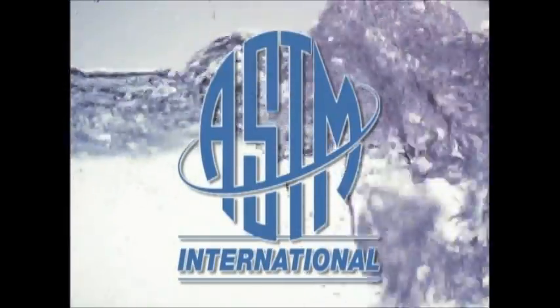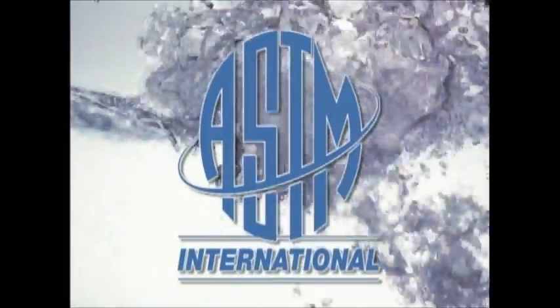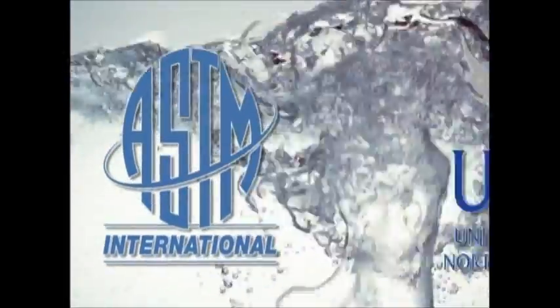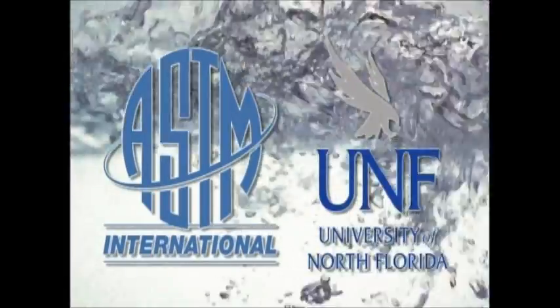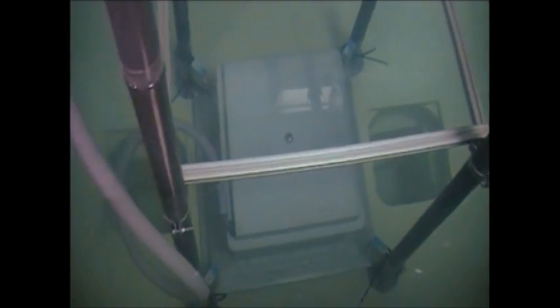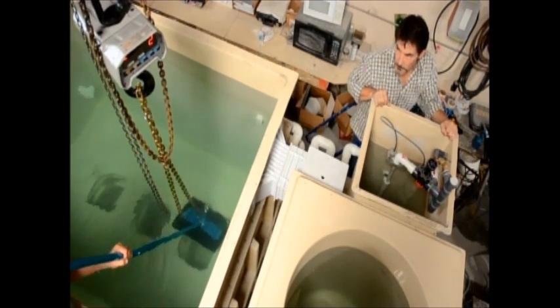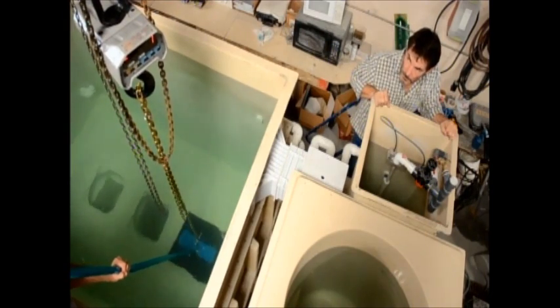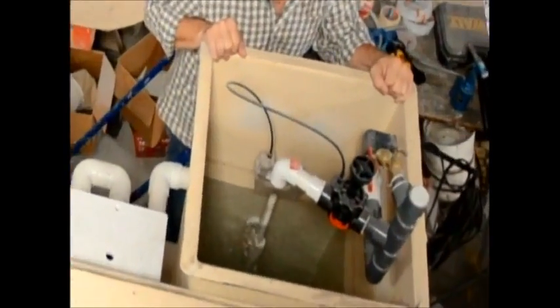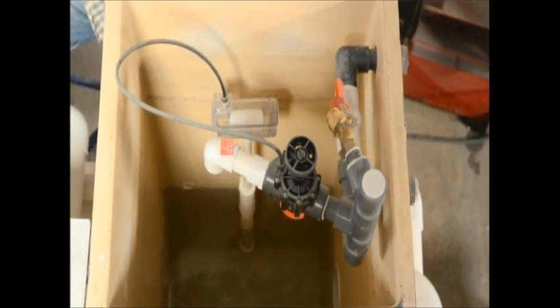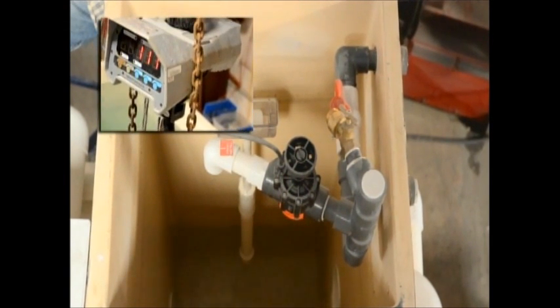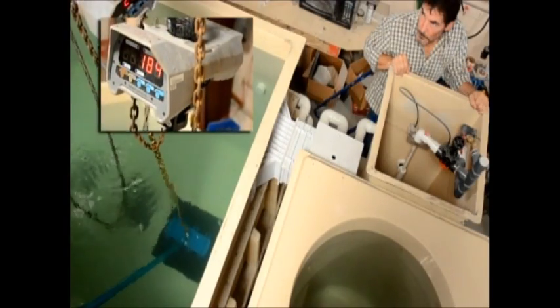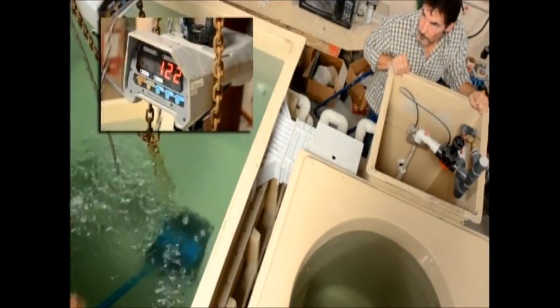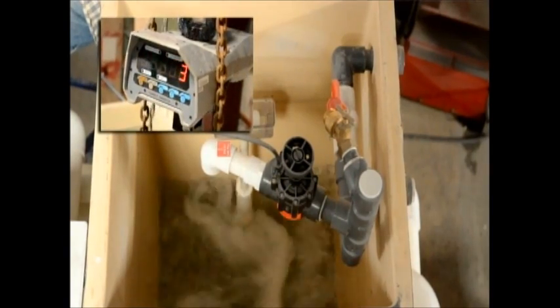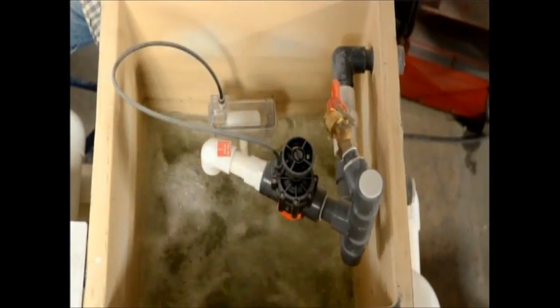To help answer some of the questions posed by the committee developing this standard, testing on gravity flow systems, the University of North Florida conducted similar tests using the same equipment that was used for the direct suction testing. A striking difference was discovered. A similar 12-inch drain sump was covered with the same device by university staff. The drain had a port connected to a collector tank. The 2-horsepower pump drew water from the collector instead of directly from the drain. When the pump was turned on, it took over 60 seconds for the force created to reach 183 pounds, or approximately 0.8 pounds per square inch.